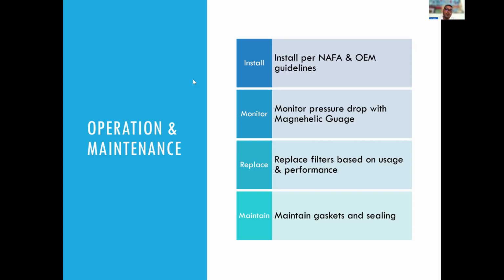Also, the newer Magnehelic gauges are great because they connect straight to the BMS, so we can look at it from the control board and see from the engineer station how much pressure we're pulling on different types of air handlers. We can replace the filters based on usage and performance. I've seen some sites where they like to replace them when it hits 1.5 on the Magnehelic. We'll talk about the TCOH report, total cost of handling, in a few moments, and the differences you can get if you change based on a predetermined preventative maintenance cycle versus waiting for the filter to actually fill up.